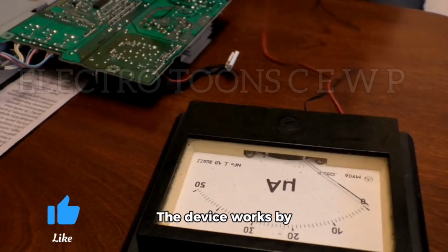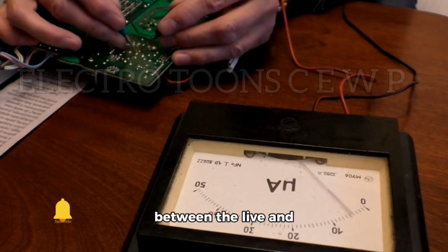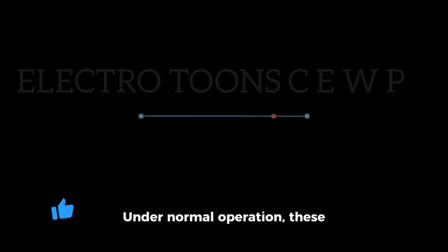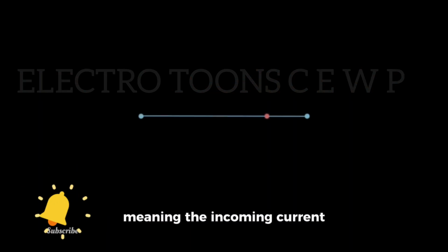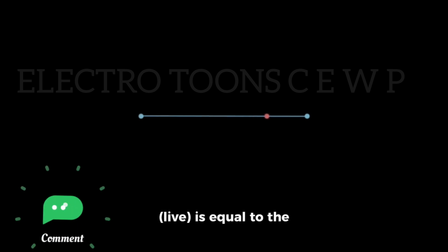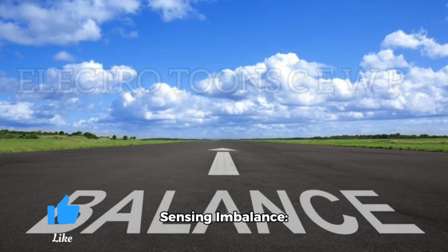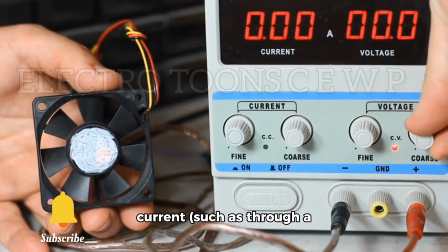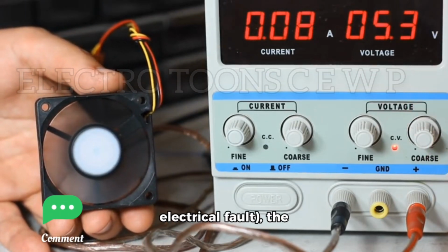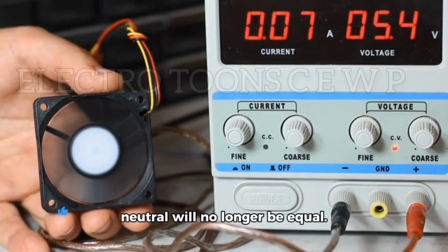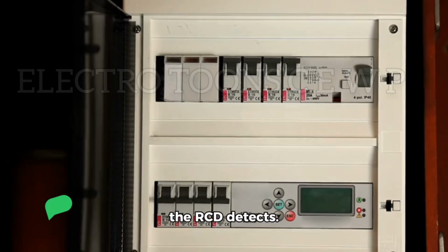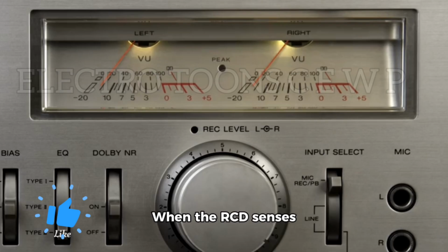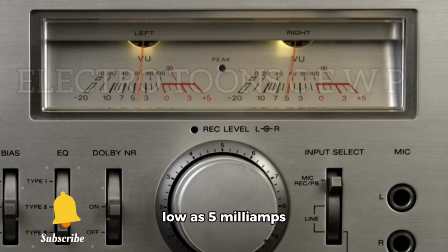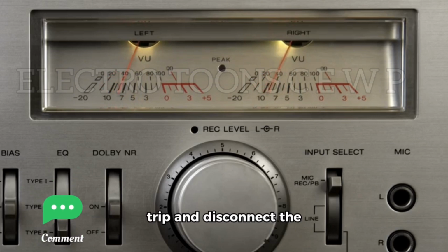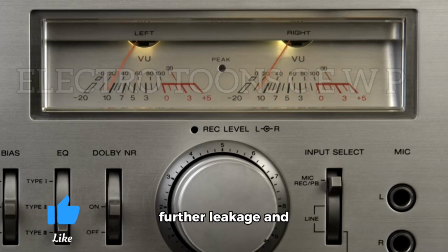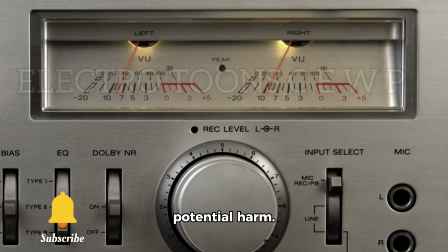Current monitoring. The device works by measuring the difference between the live and neutral wires' currents. Under normal operation, these currents are balanced, meaning the incoming current (live) is equal to the outgoing current (neutral). Sensing imbalance. If there is a leakage current, such as through a person's body or an electrical fault, the current between the live and neutral will no longer be equal. This difference is what the RCD detects. Tripping mechanism. When the RCD senses this imbalance, often as low as 5 mA, it will quickly trip and disconnect the circuit, preventing further leakage and protecting anyone from potential harm.